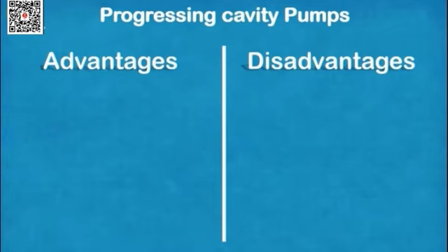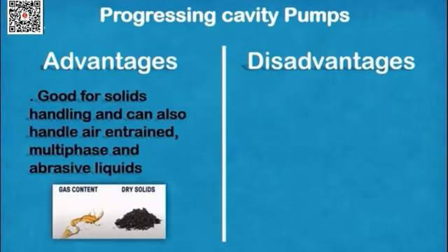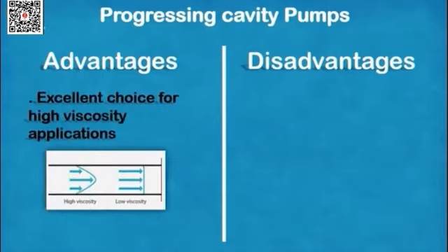There are many advantages to such pumps, like wide fluid handling capabilities. Designs can handle viscous liquids, large solids, abrasive materials, fibrous solids and gas slugs without issue, making it one of the most versatile pumps available. This pump has unparalleled viscosity handling. Viscosities from 1 cSt to 1 million mean there are no comparable pumping technologies.